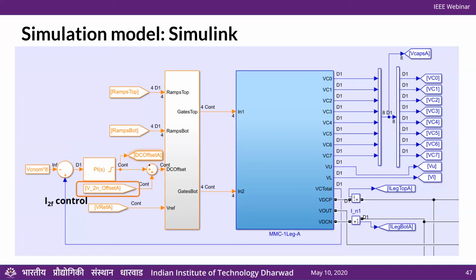The next is this 2F control, which is the DQ controller I mentioned. Essentially it measures the 3 2F components, determines what the offset should be on the 3 phases, and supplies that here. Remember, it needs to be added such that the top module gets a positive delta and the bottom module gets a negative delta. If you get the sign wrong, and end up adding offset in the same phase on both, you'll see that instead of affecting circulating currents, you'll start affecting your output current. So that's a quick check in your simulation: if you start seeing effects on the output current, it means your polarities are wrong.